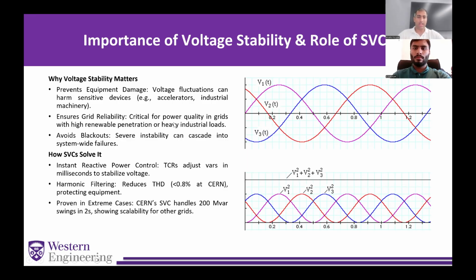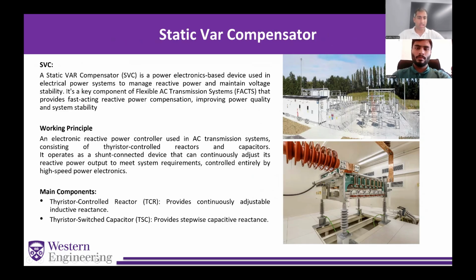So, moving on to the next slide, that is static var compensators. And in this slide, we'll give you an overview. An SVC is a shunt connected power electronics based controller that continuously manages reactive power to hold bus voltage near its set point. As you all know, built from thyristor controlled reactors, TCRs, and thyristor switched capacitors, TSCs. It blends smooth inductive control with stepwise capacitive support. The result is fast acting compensation that strengthens power quality and system stability without moving parts or slow electromechanical delays.